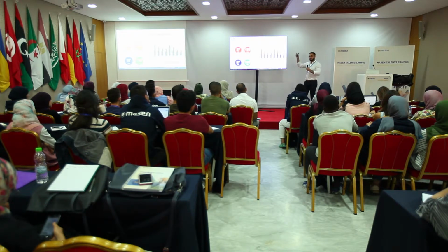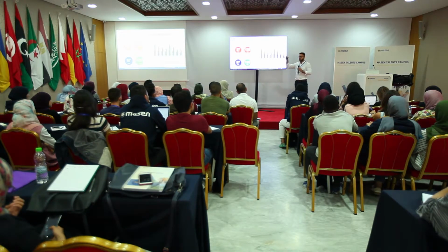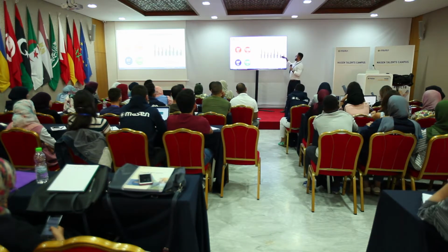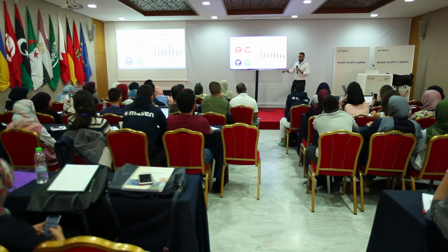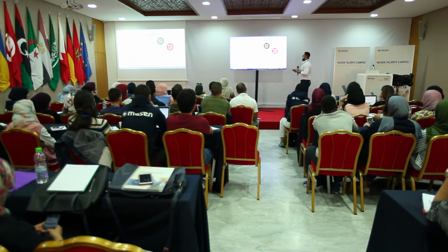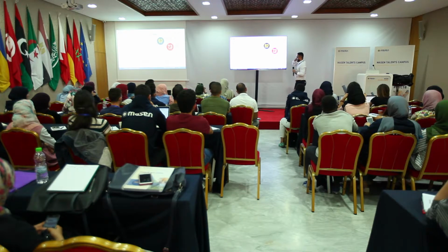Aluminum melts at 580. So aluminum is interesting because our steam cycles run at 580, and aluminum melts at 580. So if we were able to design a system where you can have aluminum in a way that during charging, some fluid is getting it hot at 580, and then you pass the cold fluid, it will end up leaving the system at 580 because the aluminum is at 580. Just an example. That's what the PCM is like.